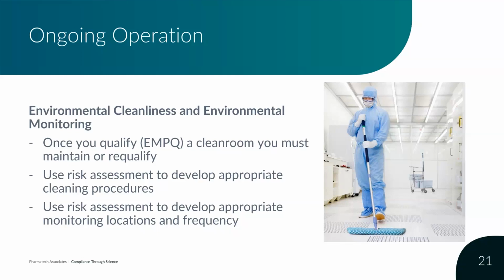So one of the biggest ways to save money using risk assessment is to decide what environmental quality you need. If you are using an isolator to do the only open processing, to load materials into a cassette or a cartridge, for example, that's going to then be put into an automated system, and that cassette and cartridge are single use, you may not need an ISO 5 clean room. Most of us don't need an ISO 5 clean room, because that quality of air is provided within the isolator, and you don't have any open processing in the room.